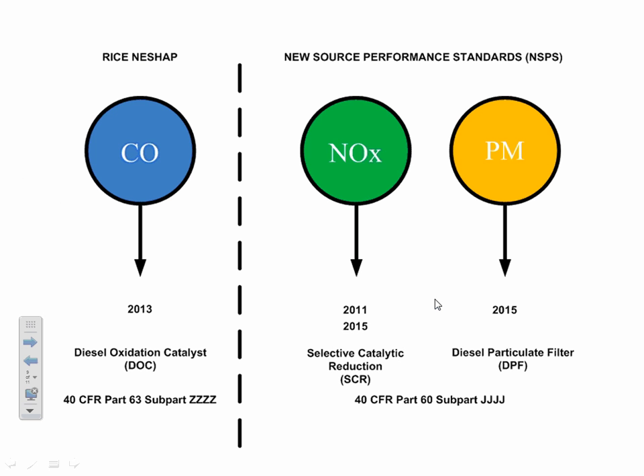I've kind of split it off in this slide I made up, just to show RICE-NESHAP is only targeting CO. It's doing that because it's the next largest pollutant next to NOx. So new equipment is more concerned with the reduction of NOx. Existing equipment is mainly concerned with CO, and CO is being addressed by basically a catalytic converter on existing equipment. Is that just for diesel? Yes. What I'm showing you so far is diesel with the NOx. The existing equipment rule does apply to spark ignited sets, so we're putting a catalytic converter on them as well. They use a filter on the very back end? Yep, you're doing a good segue for me here.